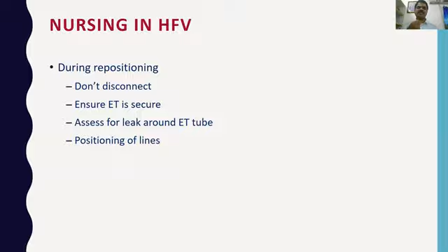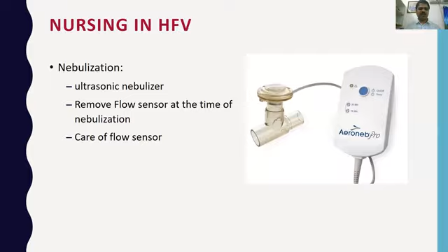And some babies may require nebulization. If there are thick or insufficient secretions, they may require nebulization. So always it is advised to use an ultrasonic nebulizer. This is the one which we use, AeroNeb, in our unit. Simultaneously, if you are using this particular nebulizer, remove the flow sensor at the time of nebulization. Otherwise, with this flow, as well as with clogging of secretion, the flow sensor will get damaged. Care of the flow sensor is very important, and the flow sensor is very costly also. If you lose that flow sensor, it's difficult to replenish.